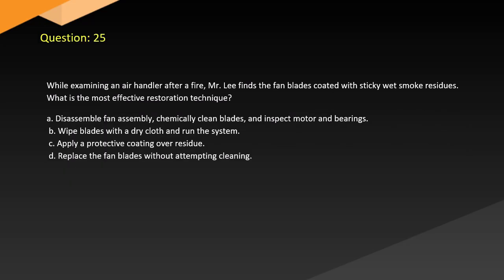Question 25. While examining an air handler after a fire, Mr. Lee finds the fan blades coated with sticky wet smoke residues. What is the most effective restoration technique? A. Disassemble fan assembly, chemically clean blades, and inspect motor and bearings. B. Wipe blades with a dry cloth and run the system. C. Apply a protective coating over residue. D. Replace the fan blades without attempting cleaning.